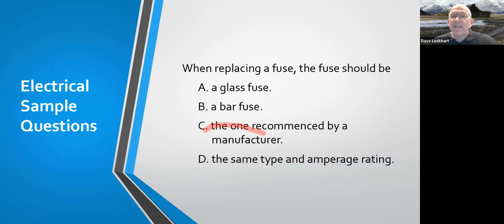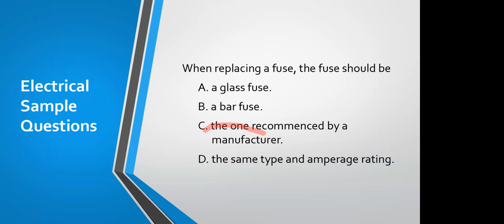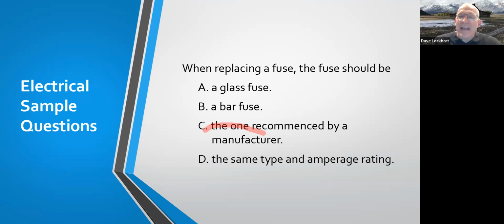All right, somebody jumped in there and said the one recommended by the manufacturer. We also have somebody that said D. Yes, D is the correct answer. The same type and amperage rating. So if you're replacing the fuse, make sure you replace it with the same type you had that was in there.